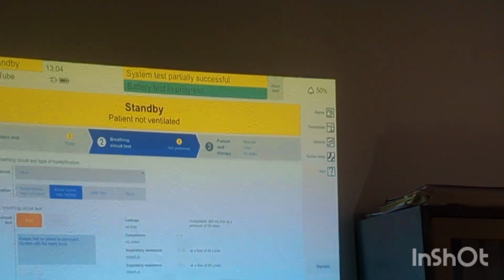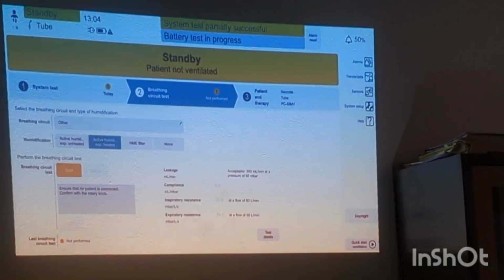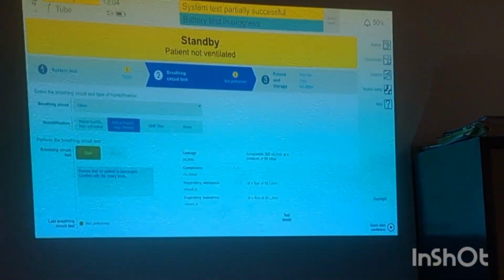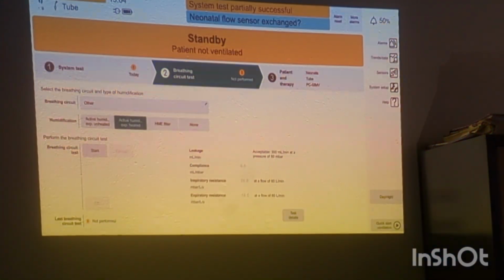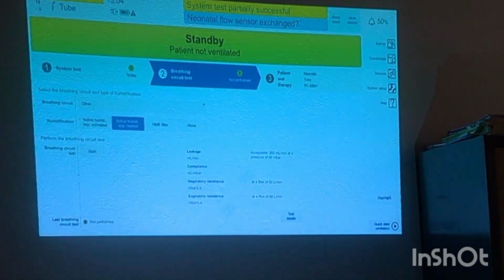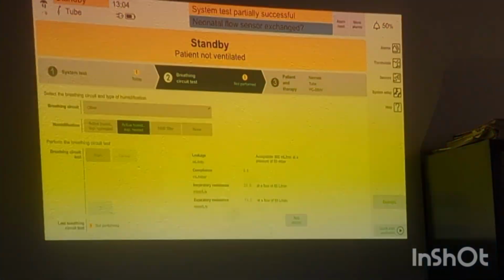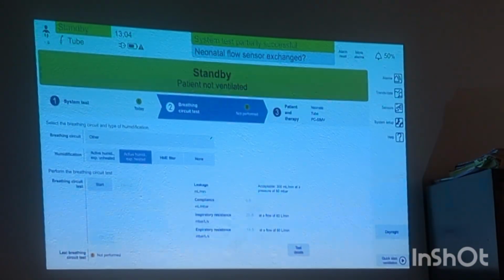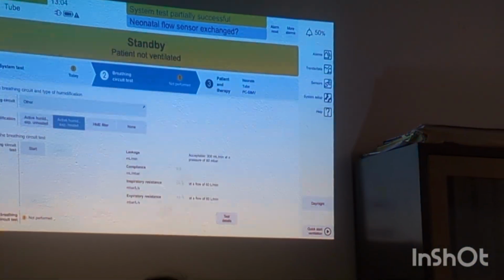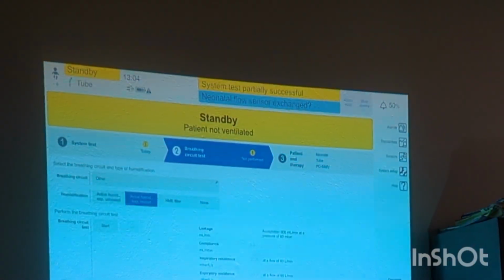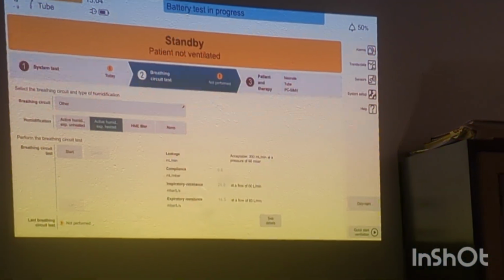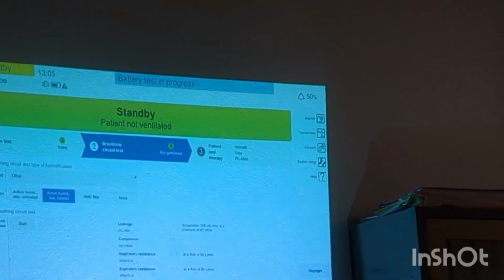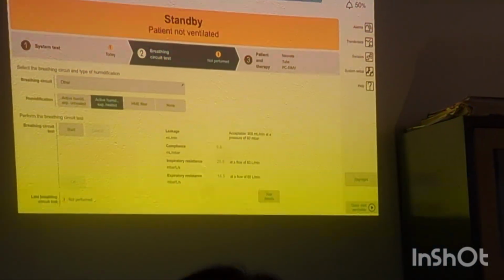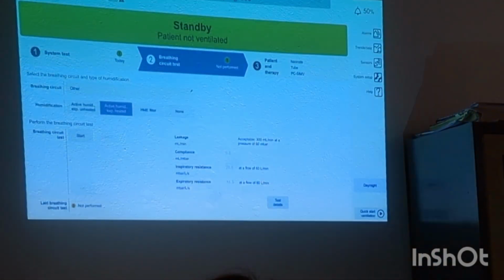Here you can see the leakage. It will also calculate the leakage, compliance, and the respiratory resistance of the circuit. It will take everything into account and compensate. Suppose there is some leakage, say 2 ml or 5 ml already there. The machine will consider that leakage and increase the flow a little bit to compensate, so that your patient gets whatever you are setting.